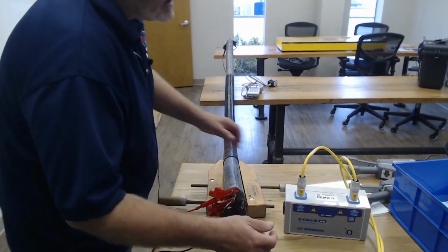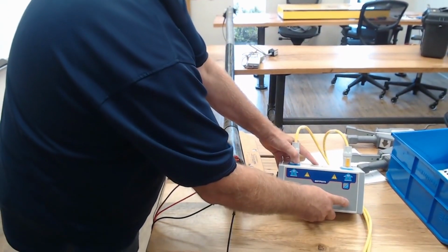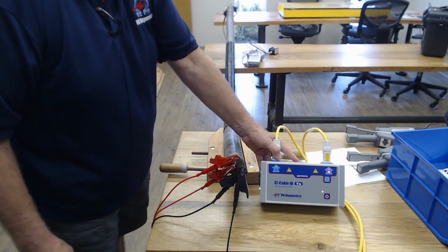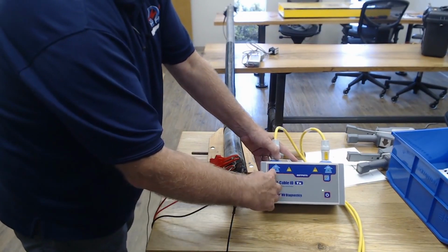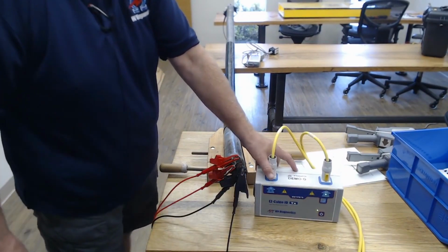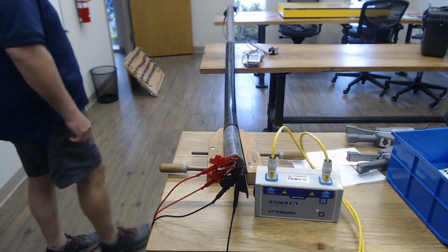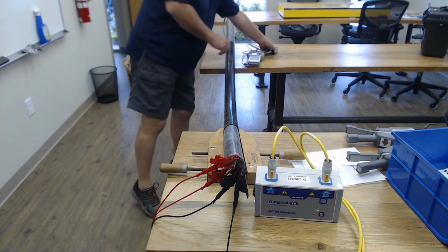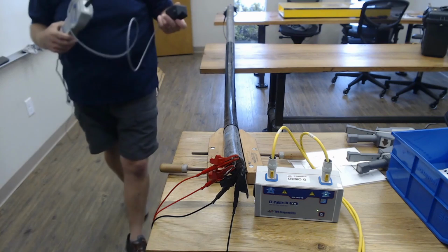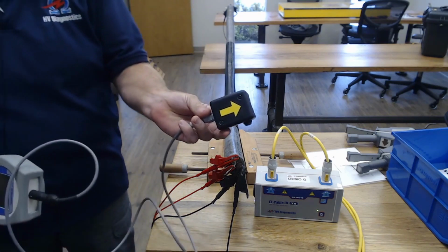All right, same deal again. We're doing a 3-phase ID. Turn it on. We want green lights. We've got green lights coming up there, which is good, which means we have a complete loop. And now because we have a 3-conductor cable, we can no longer use a Rogowski coil. Now we use this puck.